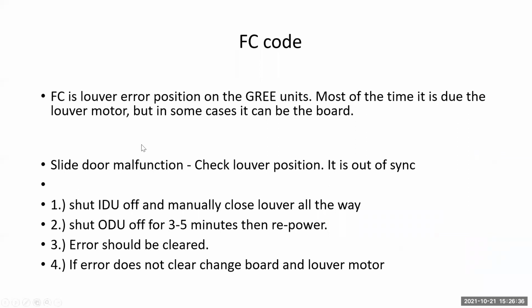And now we're looking at the FC code. This is a position code on most GREE units. It is the louver positioning, meaning the louver isn't closed all the way. Something's jamming it. Maybe the motor's not turning, or the gears are stripped. Just shut the unit off, reset the louver by closing it all the way, and turn it back on.